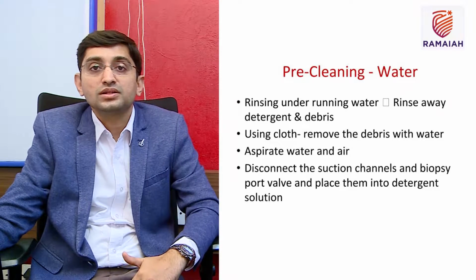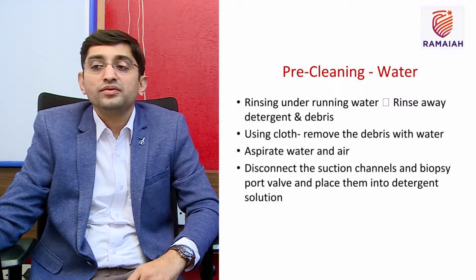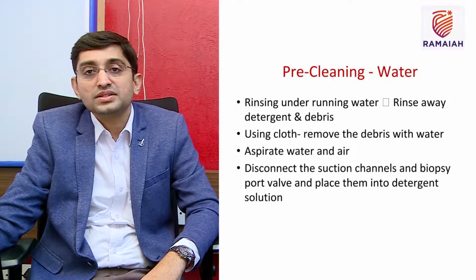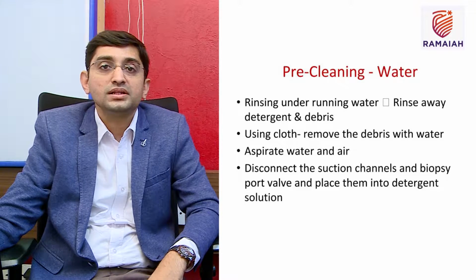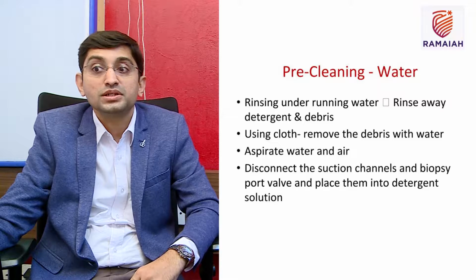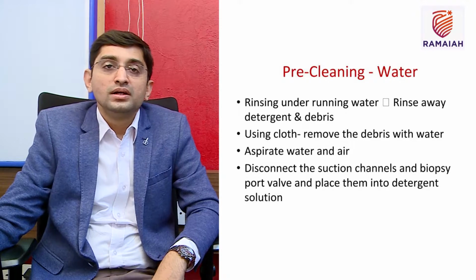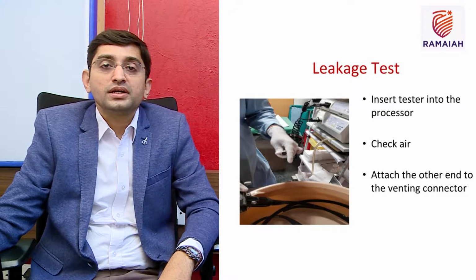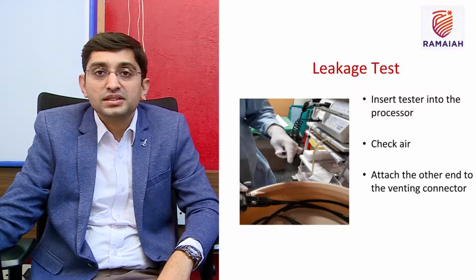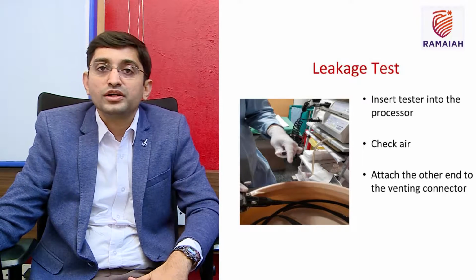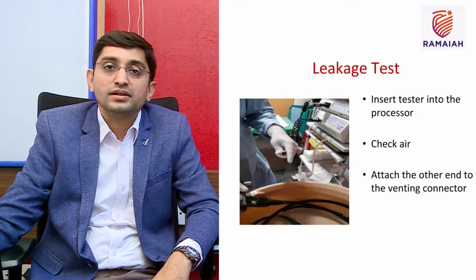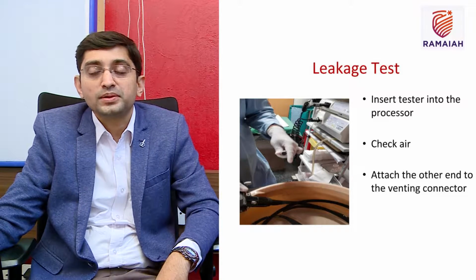We should always check the water as well as the air channel, and we should disconnect the suction channels as well as the biopsy port valve, place them in the detergent solution, and wash them separately using a small brush. Before we put it for machine cleaning, the most important thing is to check the scope for leakage, even for a routine scopy or after an endoscope which has been used for a therapeutic purpose.